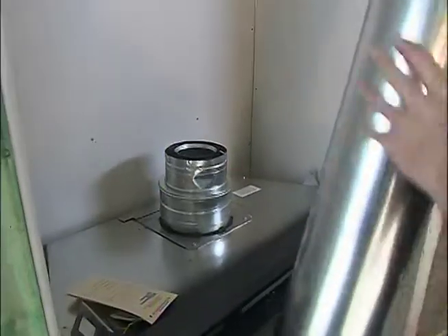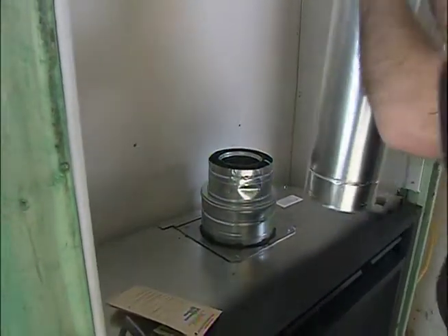So that fireplace has an insulating barrier around it so that you can frame right around it, whereas a gas insert is designed to go into an existing masonry structure. You don't have to have that insulating barrier. No combustibles here. Correct. And then the other key difference is the venting system itself.